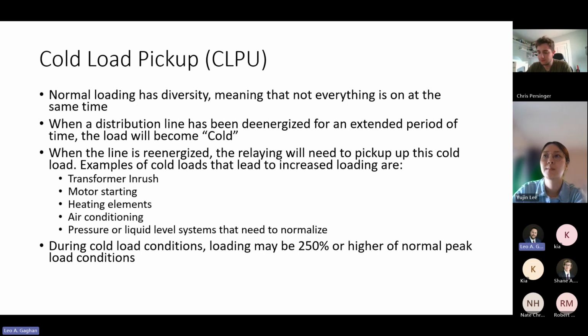So when distribution has been de-energized for a long period of time, the load becomes cold, is the term. And when that line is re-energized, the relay needs to pick up this cold load. Basically what happens with cold load is that everything turns on at the same time, or maybe not everything, but things that may not have normally all been on at the same time, more of them tend to turn on at the exact same time. Pumps have to start back up, heating systems have to start back up. Everything's got to get back to that normal place.